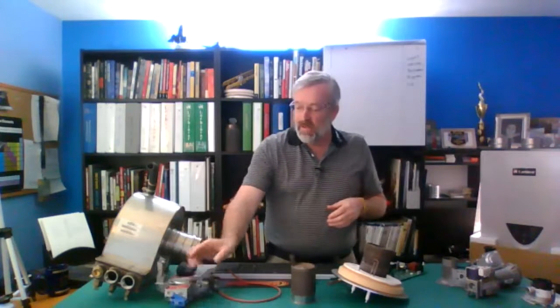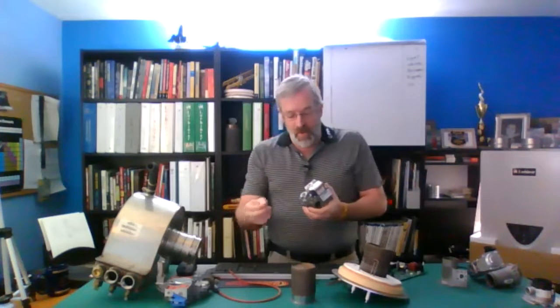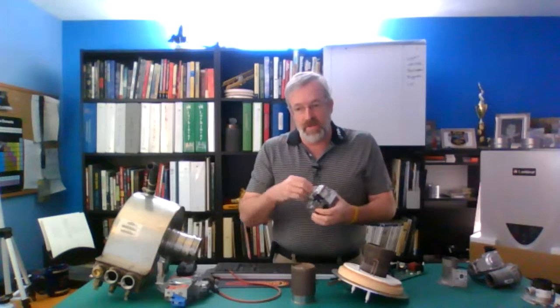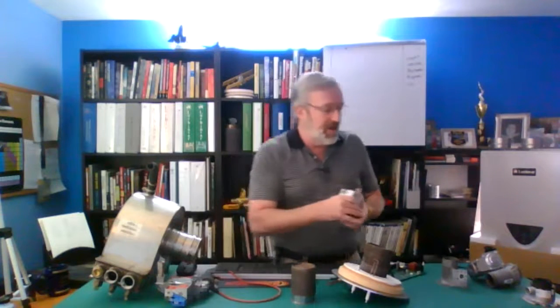So it's a blue switch on that one. When we get into the older style, it's a red switch right there. If you think it's not opening, put your hand on it. You'll feel the solenoid activate when it's getting its 24 volts. Now, the other point of keeping this plugged in as opposed to taking it off is that sometimes when you take it off, you take some of the load off, and it may work when it's not connected. Keeping it connected is definitely where we want to check for that 24 volts, to see if something's dropping out. So keep that on.